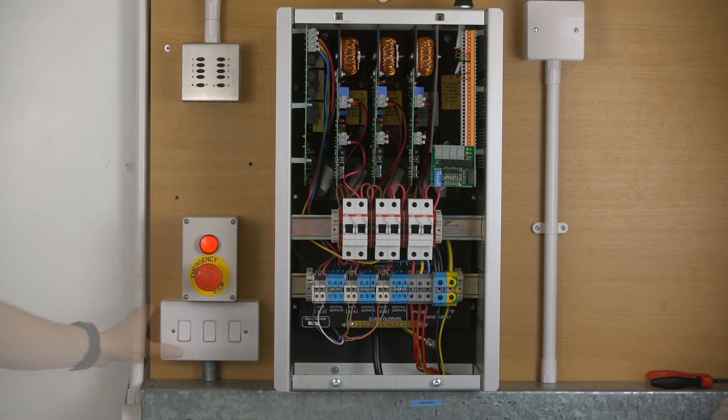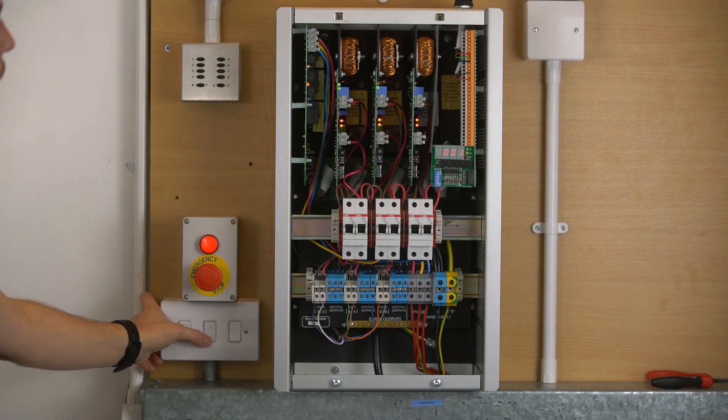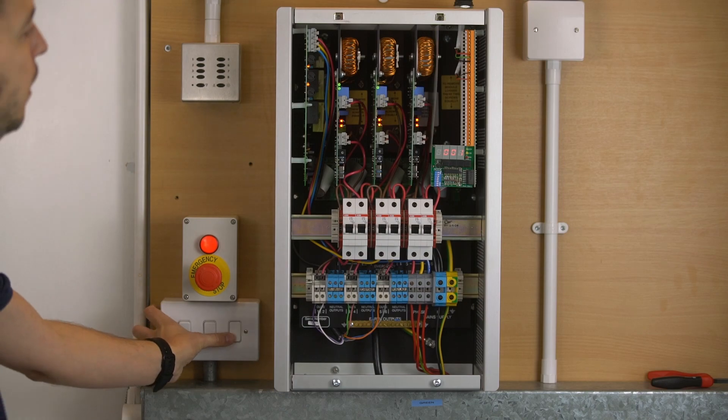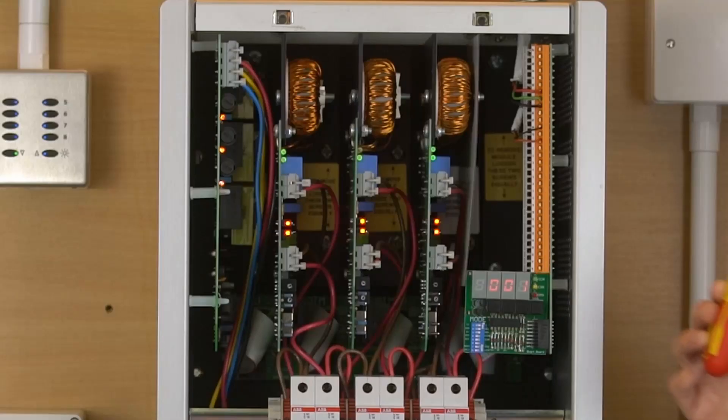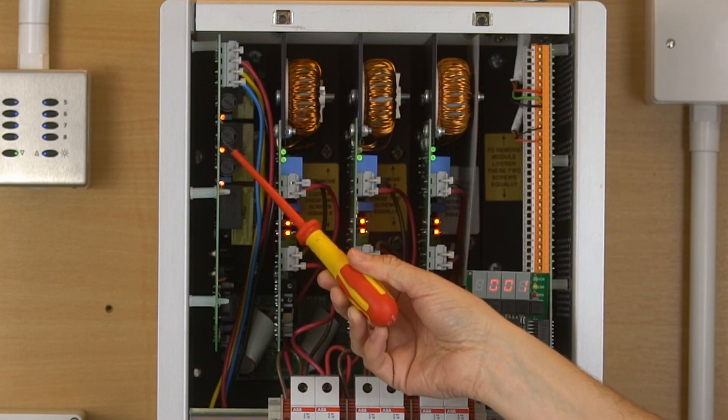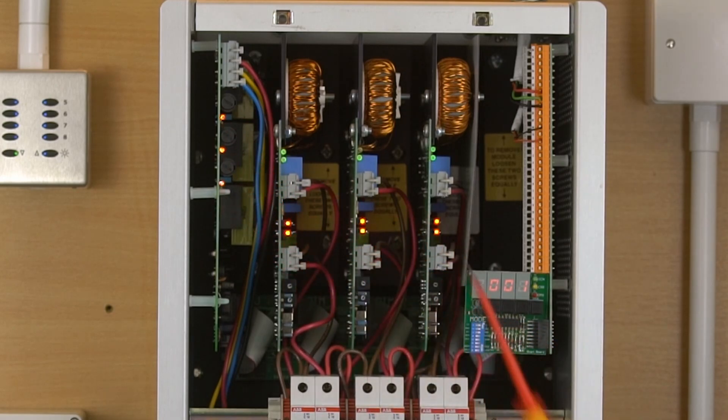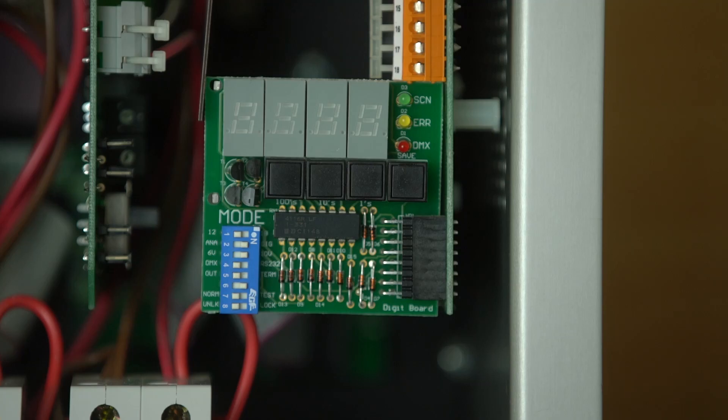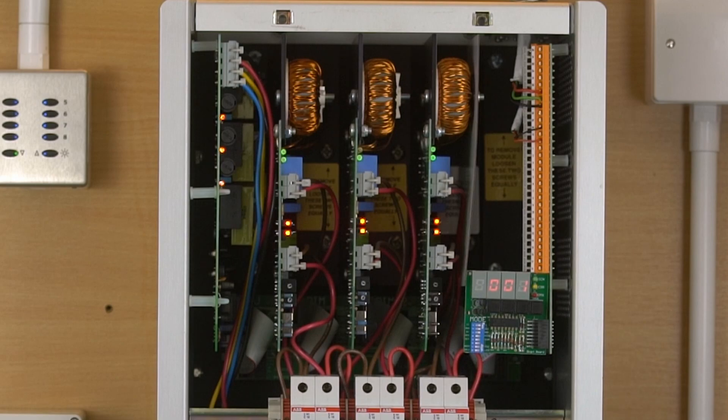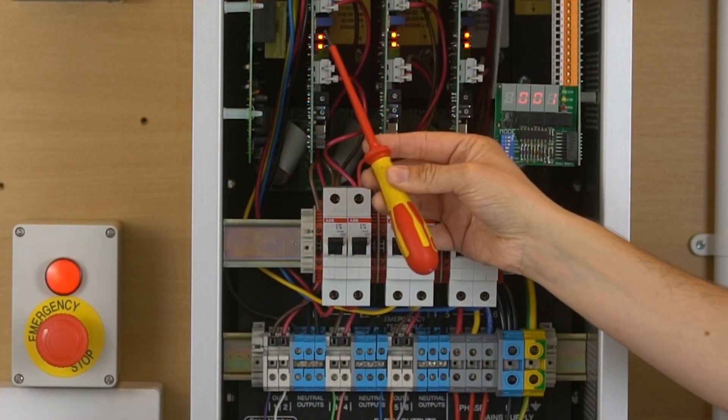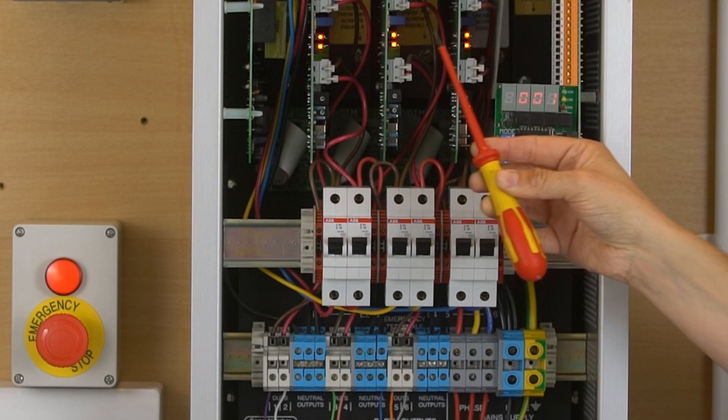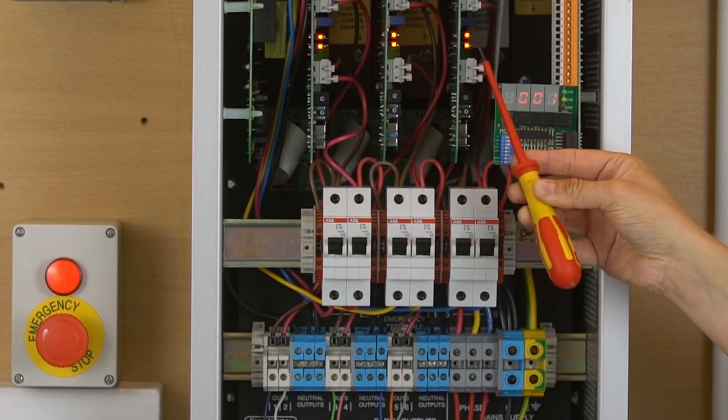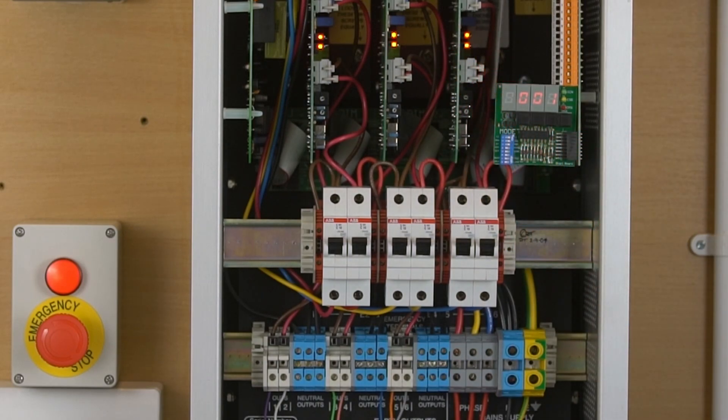And at this point you would be ready to power up your panel. Check that your three neons are illuminated on your power supply. And the display should be on 001 if it's your first pack. Make sure that your red LEDs on your dimming cards are all on.